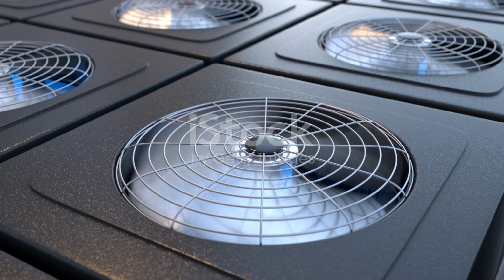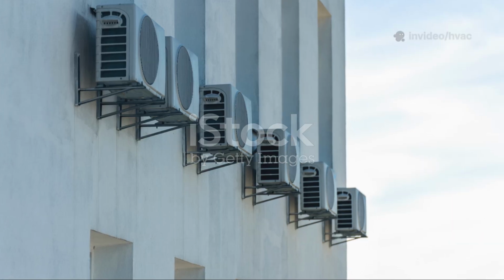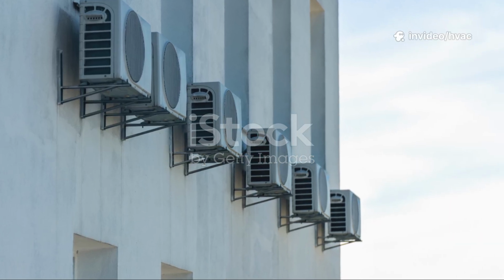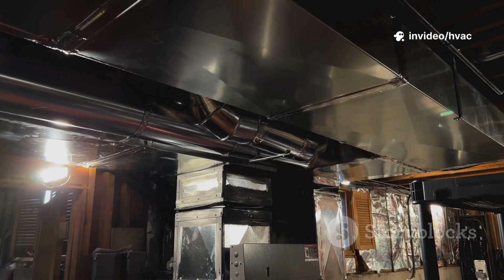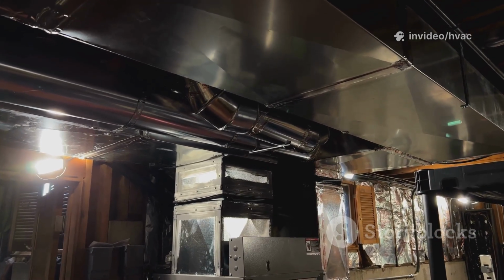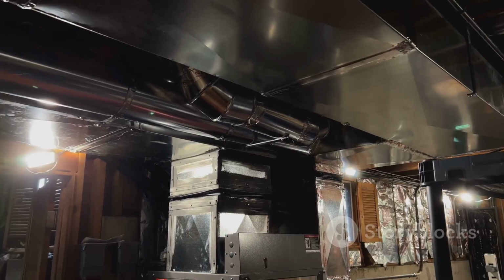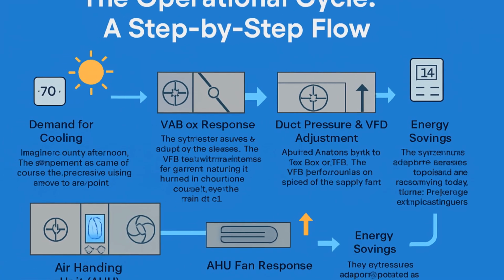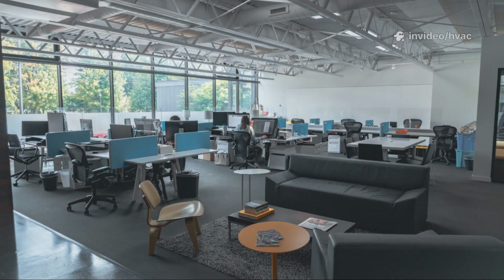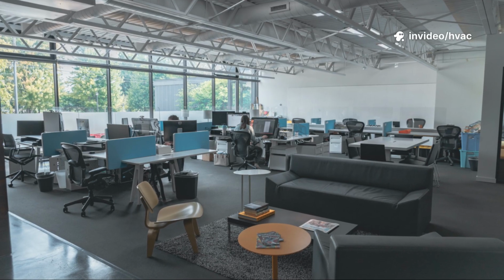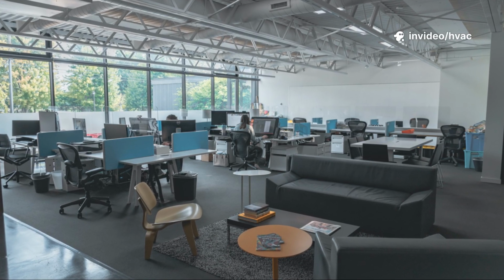Now let's focus on cooling only. It sounds limiting, but it's a huge advantage in the right building. VAV cooling-only systems skip the wasteful reheat coils. No more chilling air just to heat it up again. If a room doesn't need cooling, the system simply reduces or stops the cold air. No energy wasted. This is perfect for buildings with lots of people, computers, and sun, places that always need cooling.